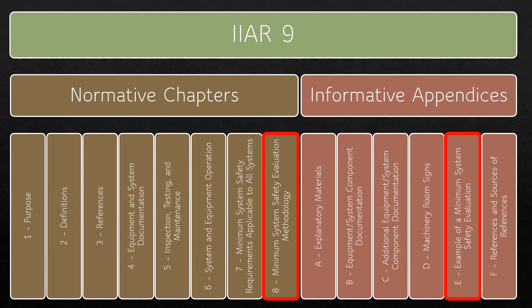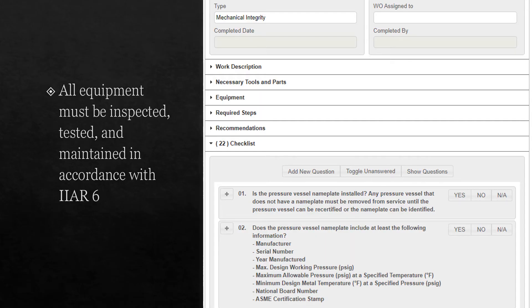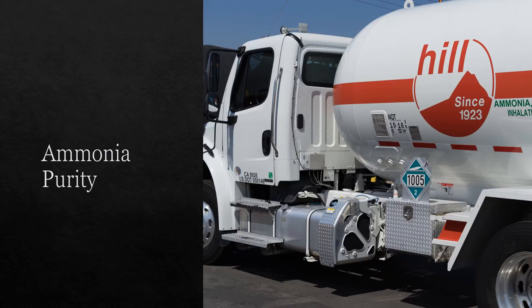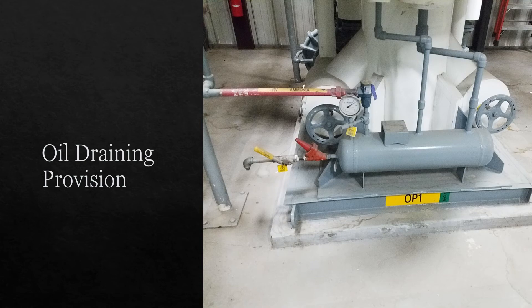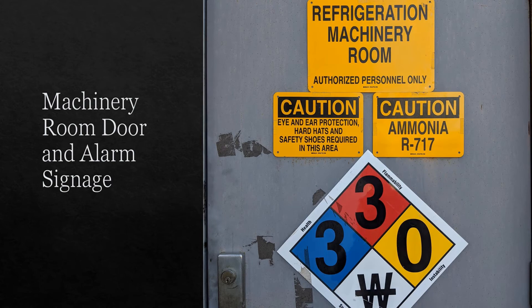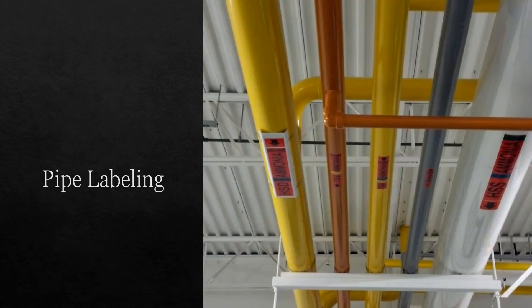To provide a big picture perspective of Standard 9, I'd like to summarize several sections that align with IIAR's existing standards. Standard 9 requires that all equipment be inspected, tested, and maintained in accordance with IIAR Standard 6. Operating procedures must be developed in accordance with IIAR 7. In general, Standard 9 contains either identical or similar requirements to Standard 2 for the following topics: ammonia purity, oil draining provision, equipment accessibility, machinery room door and alarm signage, and pipe labeling.